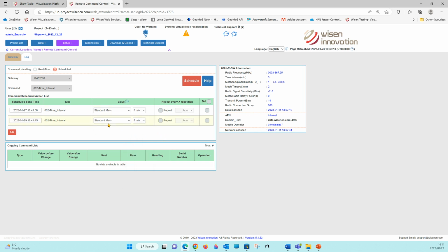Now, this is the scheduling function. One other thing to remember here is the powerful, smart system we have here in WiSen: within the warning aspect, we can set the T interval to change with the trigger threshold. So if we hit a green, an amber, a red, or a black, we can increase the time interval to suit. And obviously, if we revert back through those trigger levels, it can slow down. So that's an automated system based upon trigger alerts to increase and inform you if there's something untoward.